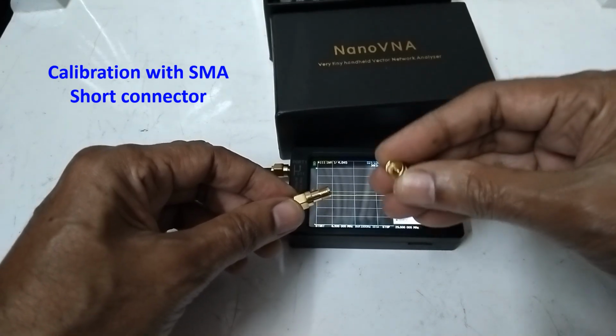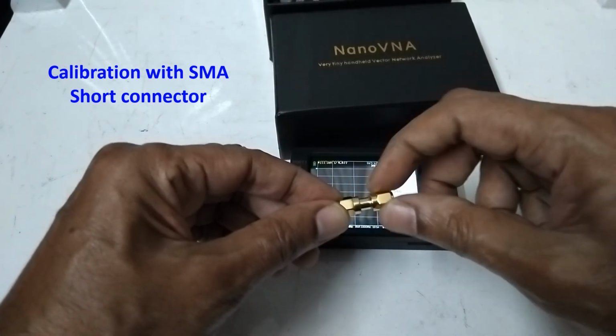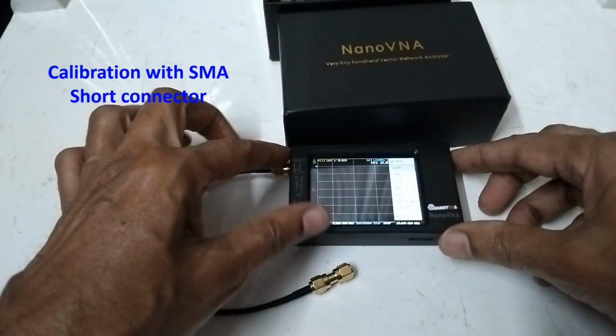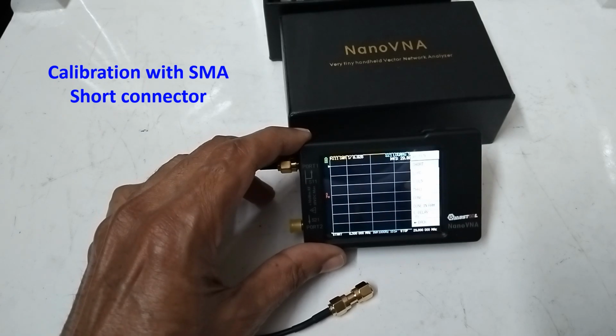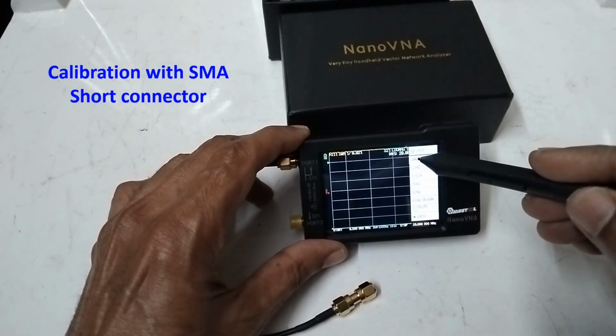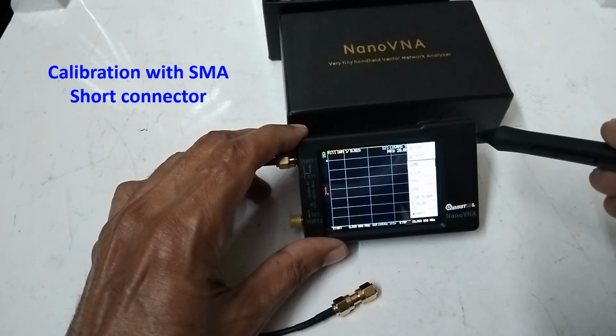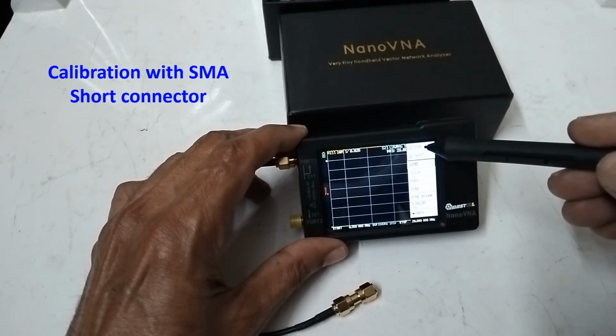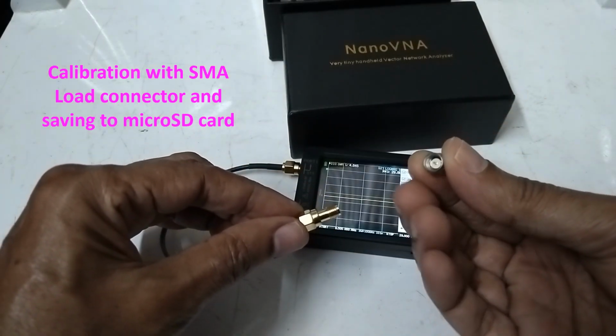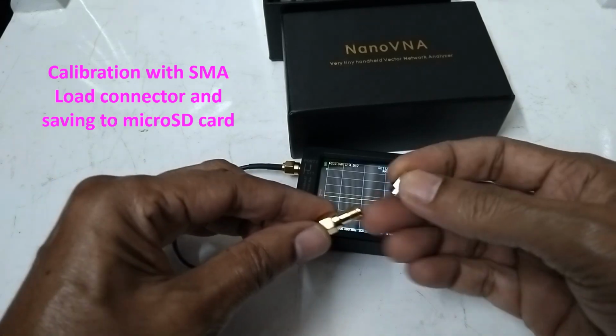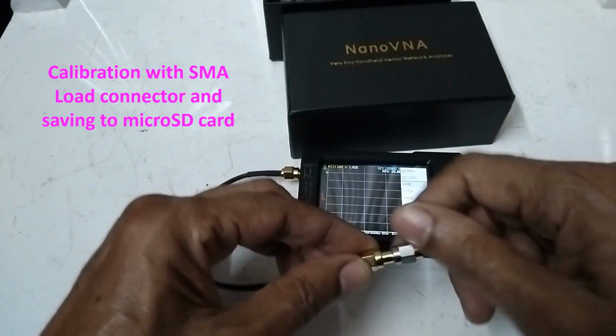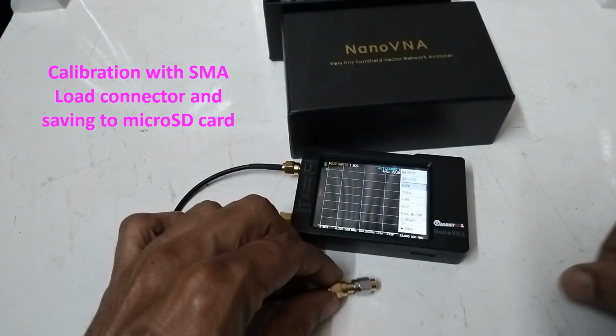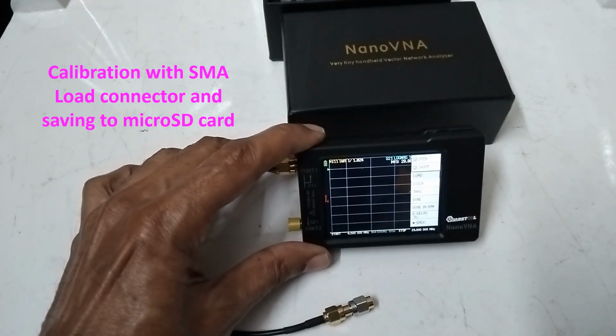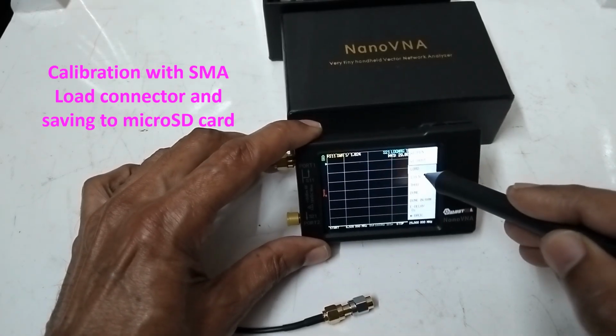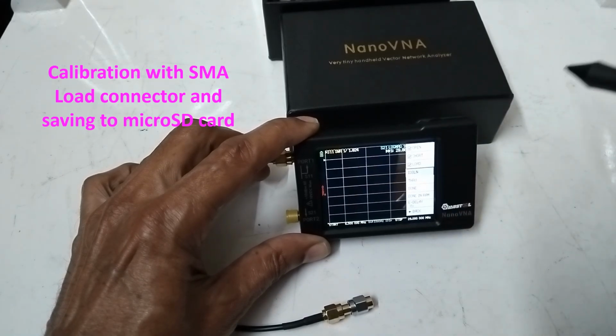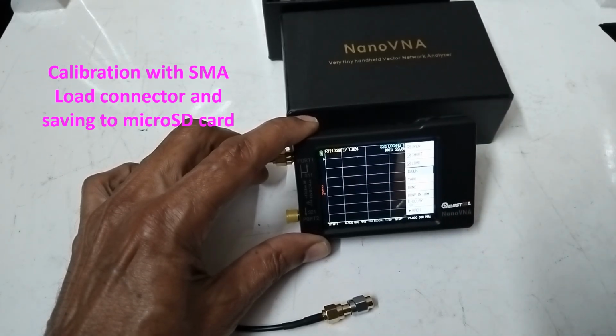This is the SMA short connector. I have connected the SMA short connector. Now again calibrate the SMA short. It has been calibrated. You would have seen a blue line running and the tick mark has come here. Now the SMA load, 50 ohms load, this is having a silvery color, that is being connected. SMA load has been connected, and for calibration again you press on SMA load. Again a blue line had been seen and tick mark has come.